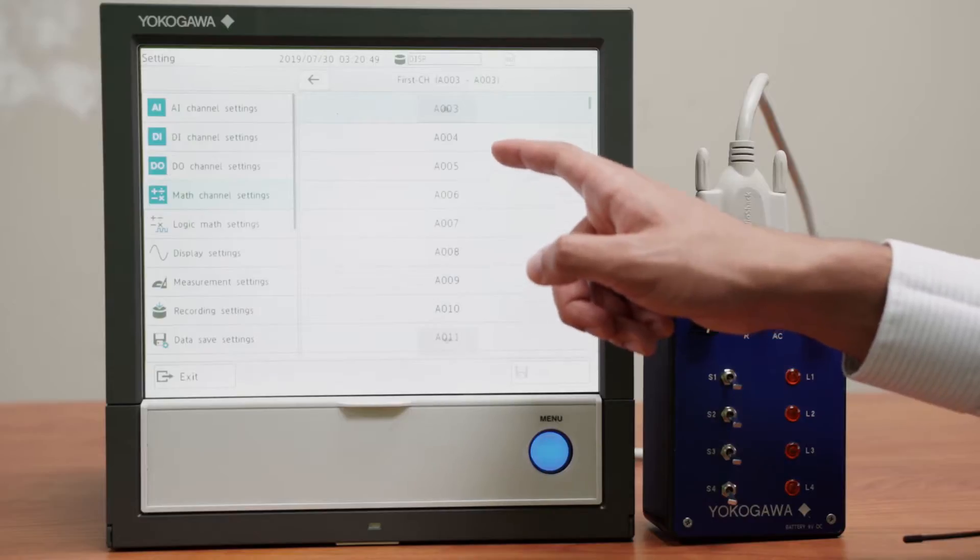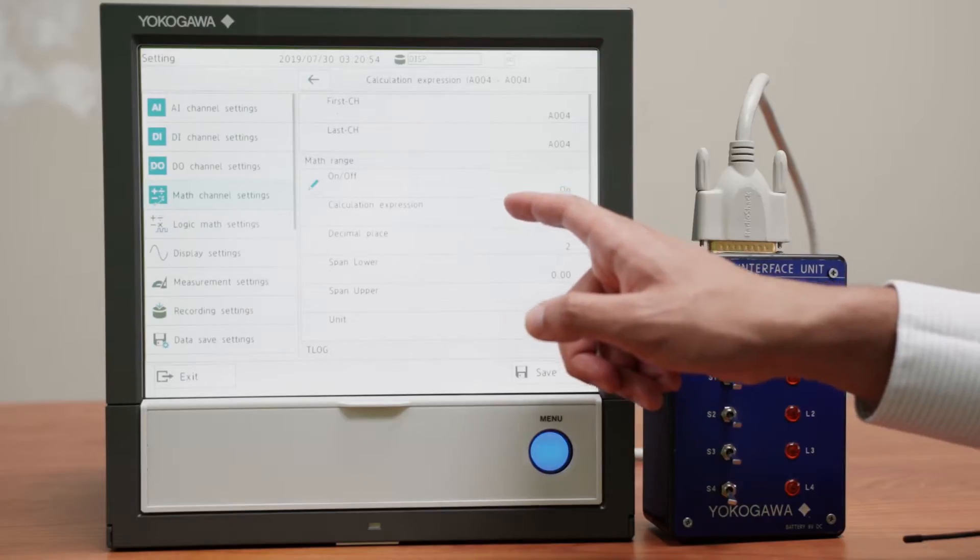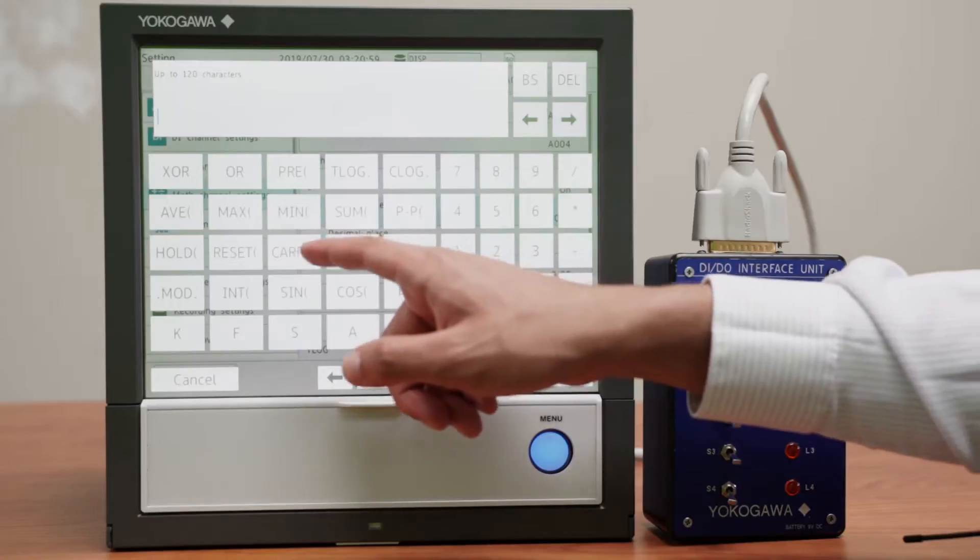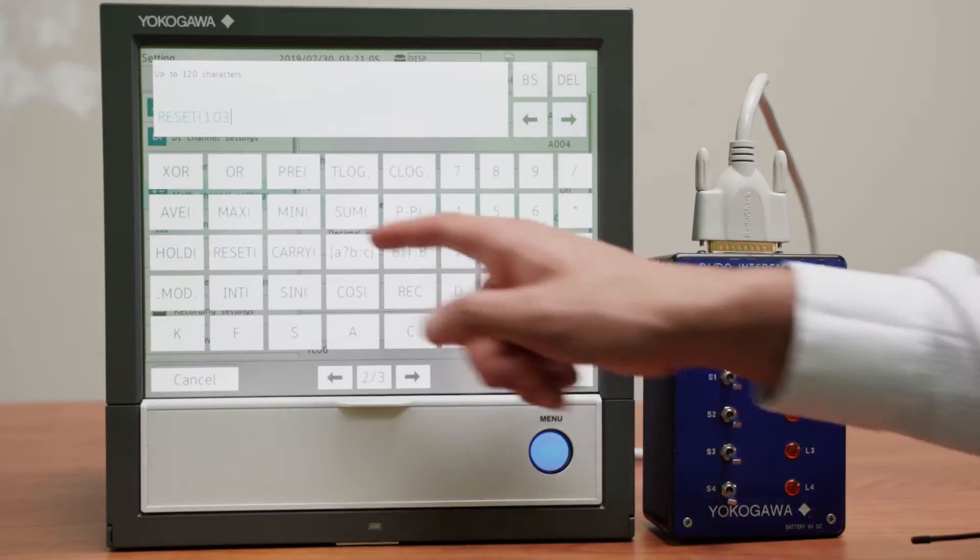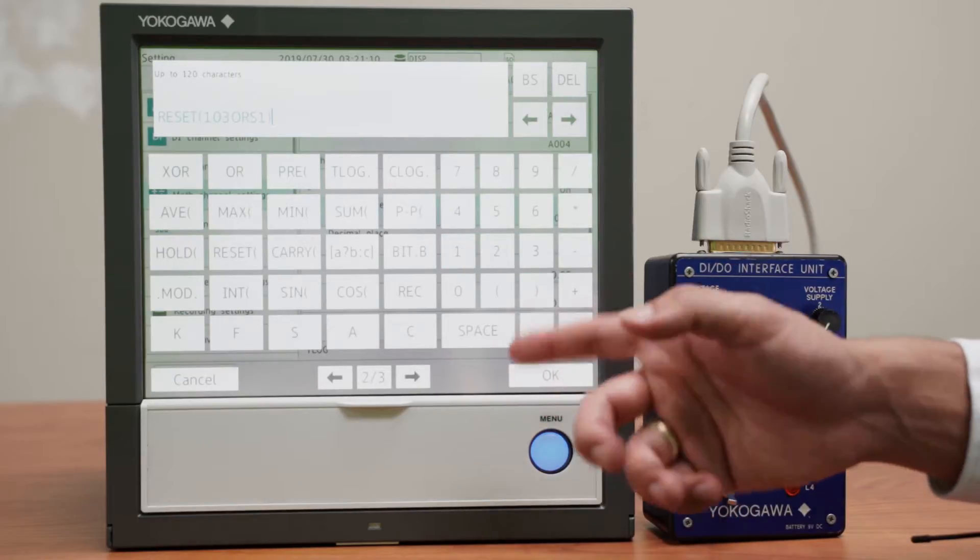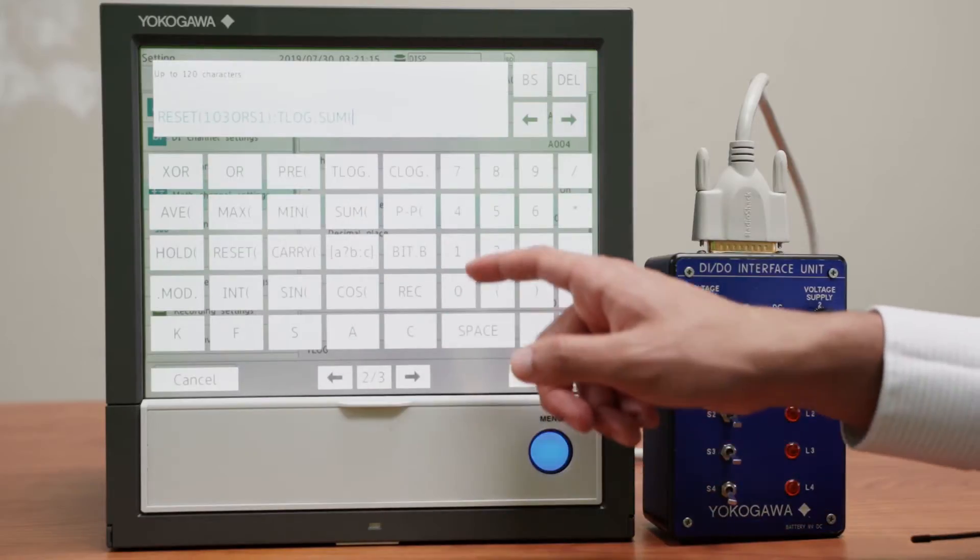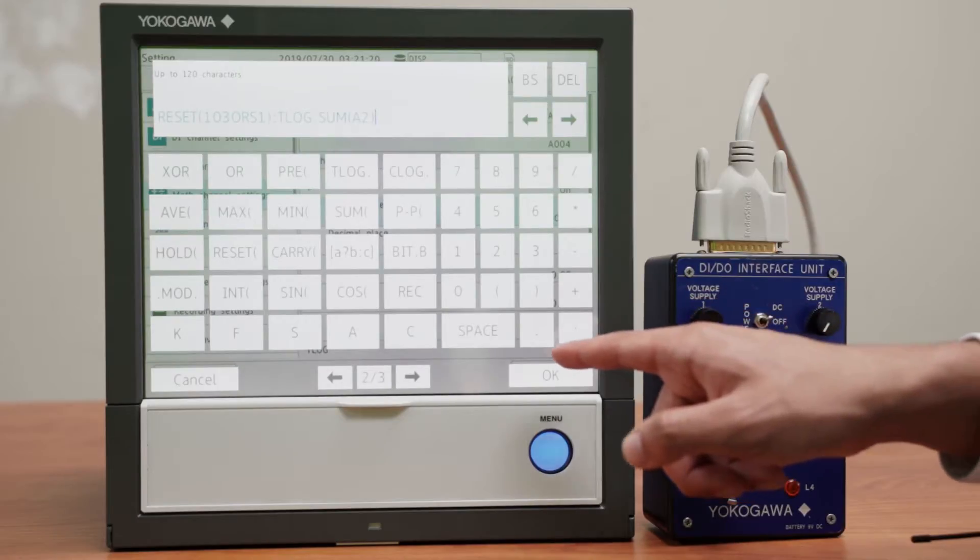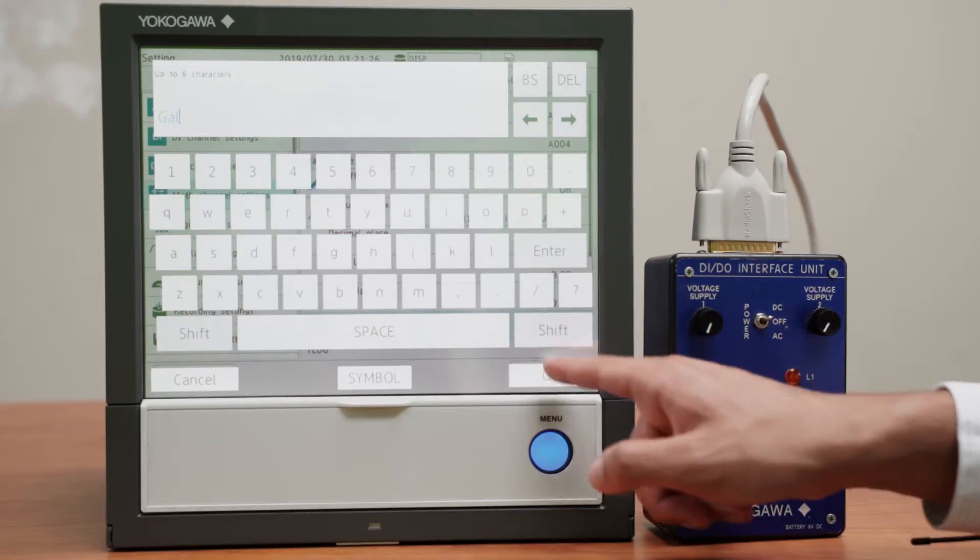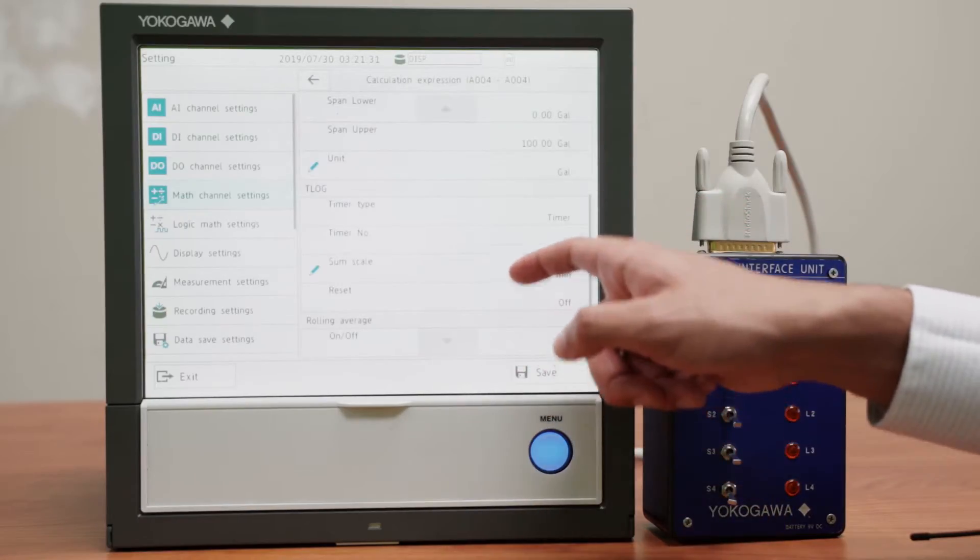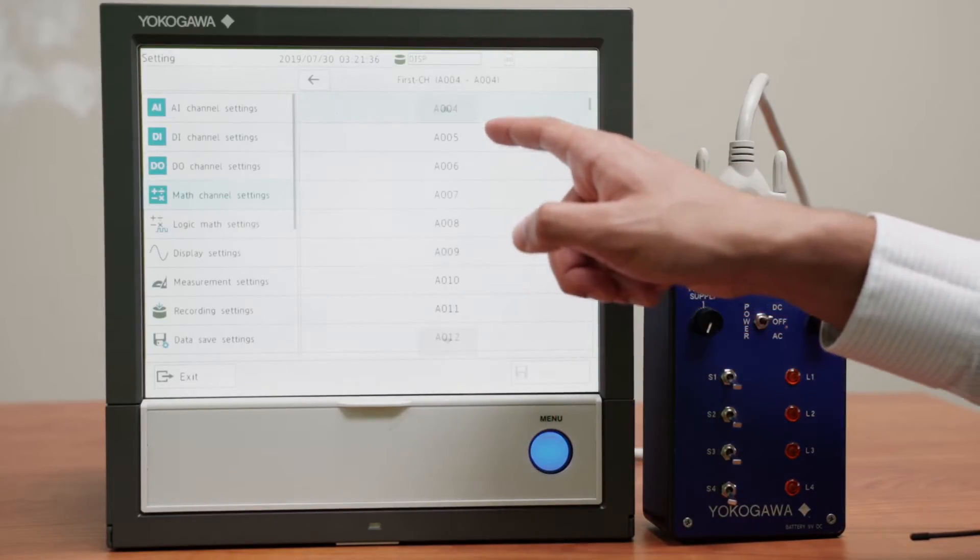We do the same for channel A4 except this will be a summation of what is going out and not in, so reset channel 103, which is this switch, or our switch number 1, which will be an internal switch, not a physical one, t-log sum of channel A2, which is all of the water coming out. This will be in gallons as well. And we need to change our sum scale to minutes, and that is it for channel A4.